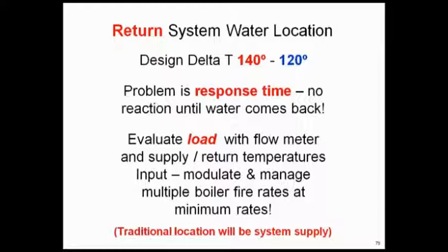Now we very seldom do this simply because of the response time, so don't walk away thinking that's the answer. I just want you to understand the impact of where you put your controls and what happens. The return water side would keep you condensing, but most people don't go there because of response time. Once you fire the boiler, how long does it take that gallon of water to get through your whole system and back to the sensor? It might take several minutes, and you could be in trouble doing that.